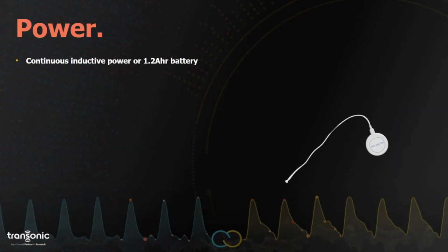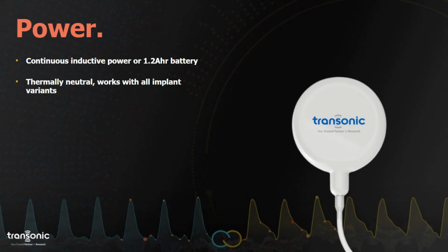Like all implants, we require a power source. So there needs to be some way of providing power to this implant. On our side, we have 2 different options. One option is to go with a battery source. That's a 1.2 amp hour battery. The other is our continuous inductive technology. Given that the value of this data is very high, we also get feedback from our clients that the most suitable option for their needs is continuous monitoring, which partners very well with the inductive power. Less a feature and more a requirement for this type of technology is for this to be thermally neutral, which fortunately ours is.